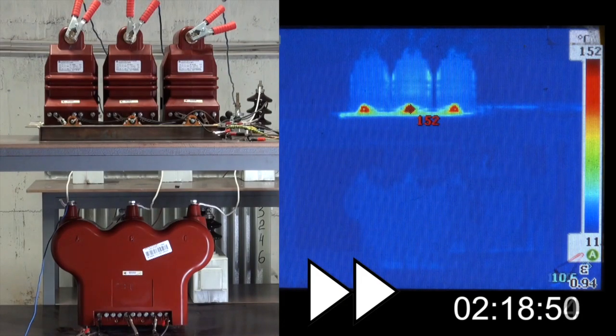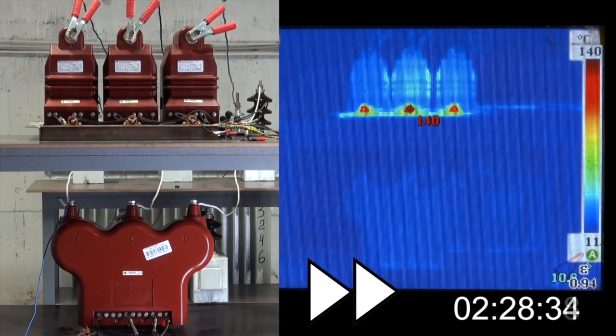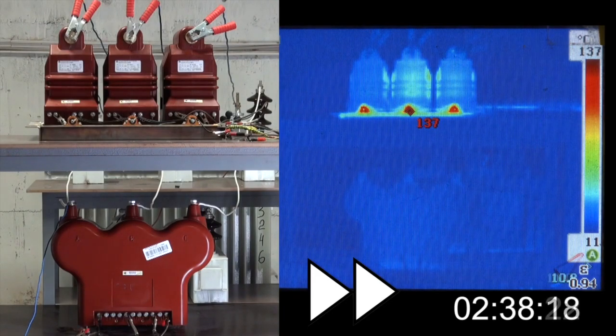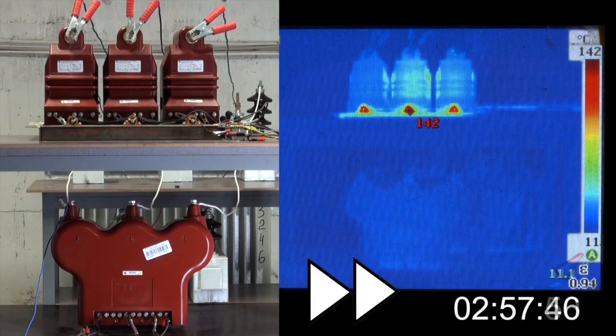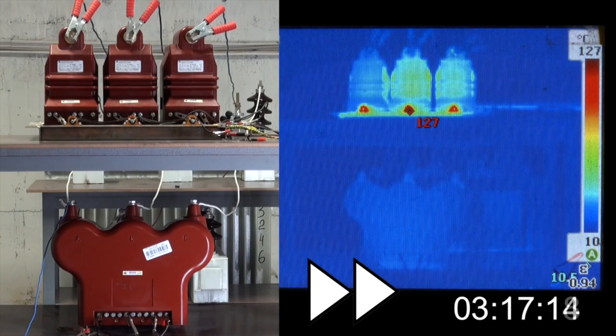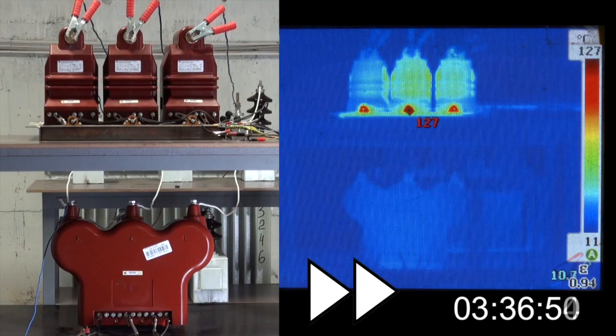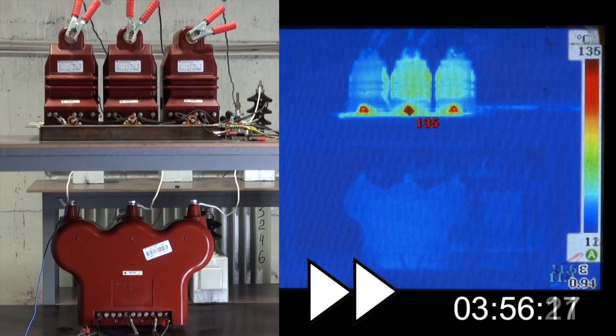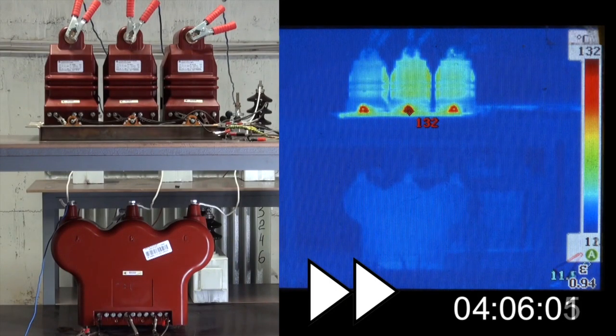During arc faults to earth, an extremely high current flows through the primary windings of single-phase voltage transformers. It exceeds not only the rated current of the primary winding, but also the maximum permissible one. At the same time, voltage surges are constantly observed. These currents lead to rapid heating of the resistors in the neutral of the transformers, which are primarily designed to reduce the effect of currents on the transformer windings. After some time, the first of the resistors fails. Following it, the first transformer, of phase B, fails.